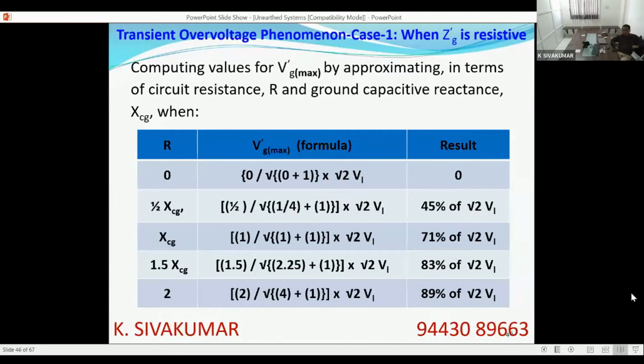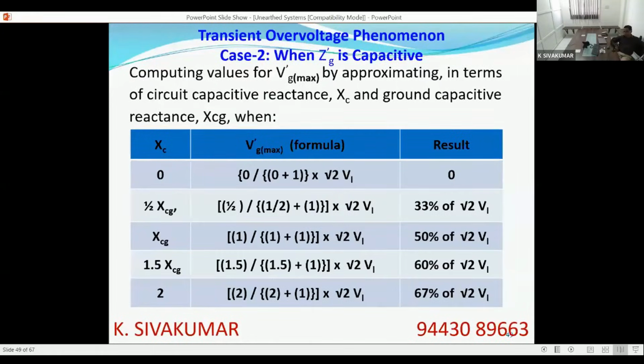If the external capacitance is 0, if the external capacitance is 50% of the leakage capacitance, 33% voltage. If the external capacitance is 100% of the leakage capacitance, 50% voltage. If the external capacitance is 150%, 60%. If the external capacitance is 200% of the leakage capacitance, 67% voltage.